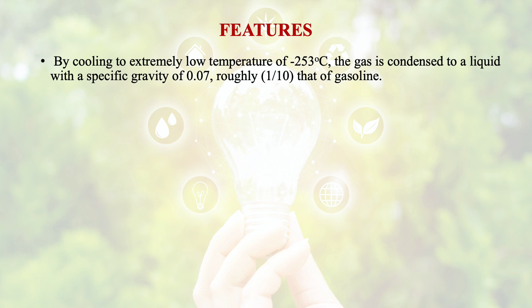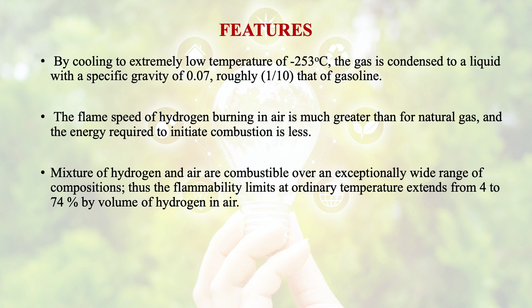If we talk about the flame speed of hydrogen burning in air, it is much greater than that for natural gas, and the energy required to initiate this combustion is less. So to initiate the combustion in the case of hydrogen gas, we need a smaller amount of energy than for natural gas. Mixtures of hydrogen and air are combustible over an exceptionally wide range of compositions. Thus, the flammability limits at ordinary temperature extend from 4 to 74% by volume of hydrogen in air.